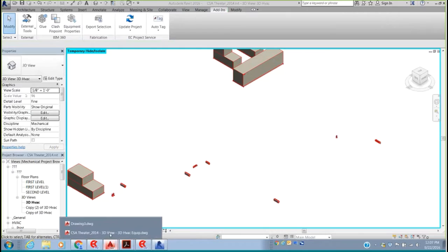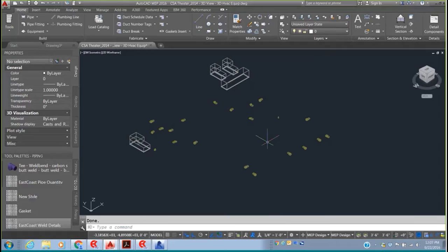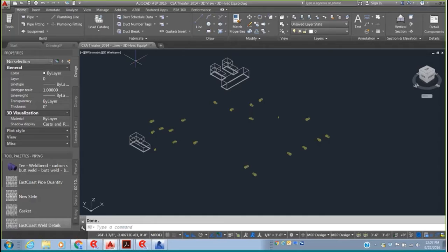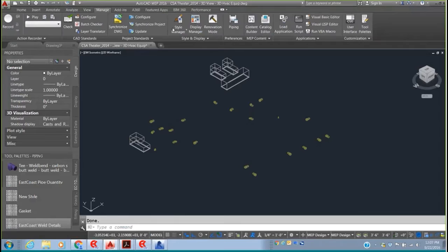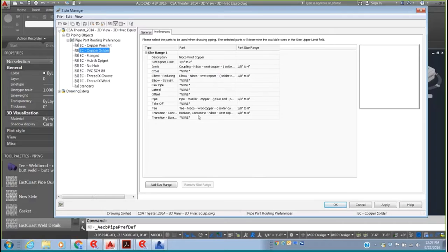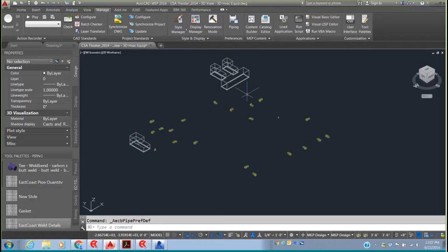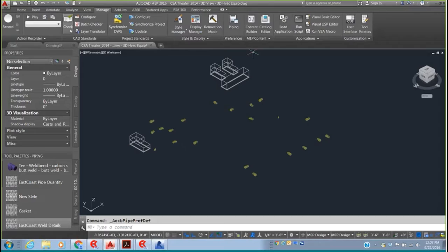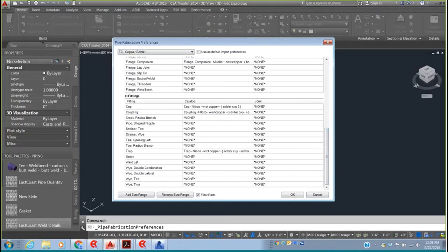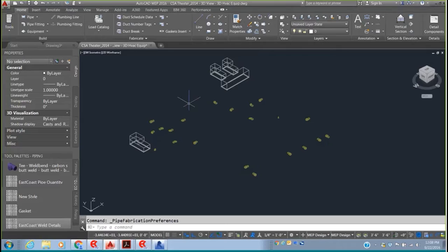Moving to AutoCAD MEP, I'll open a drawing with equipment already on it. The routing preferences tell AutoCAD MEP what fittings to use. Going to Manage > Pipe Routing Preferences, I select 'copper solder' — I've specified Nibco fittings and Mueller copper pipe here. That handles pipe, elbows, tees, reducers, and joints. For other items, I go to Pipe Fabrication Preferences: for example, a ball valve with lever handle maps to a Milwaukee bronze solder valve. Caps, traps, and similar fittings are also mapped here.